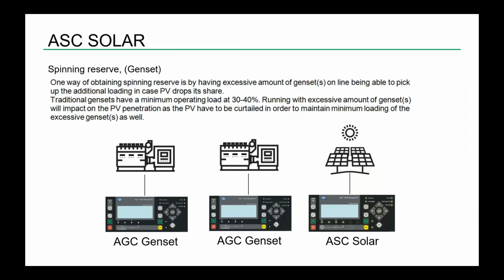I mentioned earlier the spinning reserve. Spinning reserve is a power management functionality for the integrated solution. If we talk about the dynamic spinning reserve, then we reserve a portion on the generator, so the generator can always supply this amount of power. So let's say our set point is 50%. Then if the PV is producing 100 kilowatt, 50% of this is 50 kilowatt. So the generators can always provide an additional 50 kilowatt. And maybe during midday you produce 500 kilowatt of solar. So now they will reserve 250 kilowatt. So you see, it's a dynamic value.